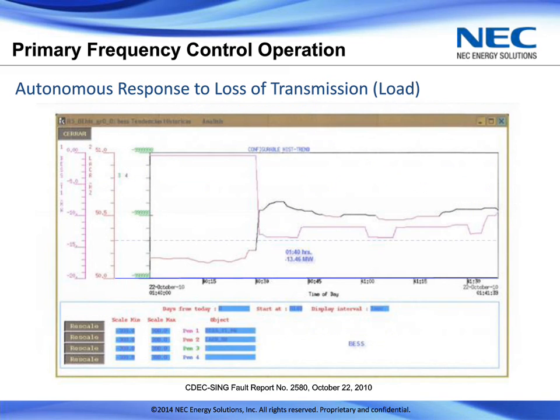In my next slide, I'm showing sort of an opposite case where there's a disturbance in the grid again, but this time it's a loss of transmission, a loss of load. And you'll see the same response, whereas the frequency starts to rise above tolerable limits, the BESS then goes into full charge mode, pulling off the extra power, acting as a controllable load to help, again, stabilize the frequency against that sudden disturbance.